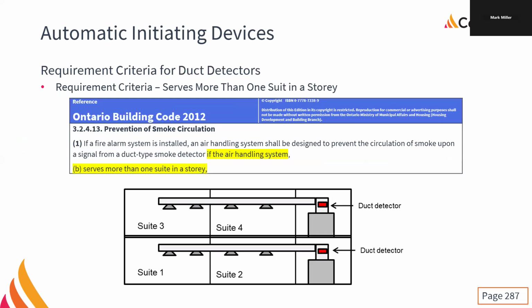If we're serving more than one suite, that could be office suites, it could be apartments, anything like that. If we're serving more than one suite, we have to be able to shut it down. So we're going to have a duct smoke detector, and this air handling unit is going to shut down on a signal directly from the duct smoke detector because you can get relays in them, or it'll shut down right from the fire alarm control panel via a relay. And we'll be talking about that again in Module 8.